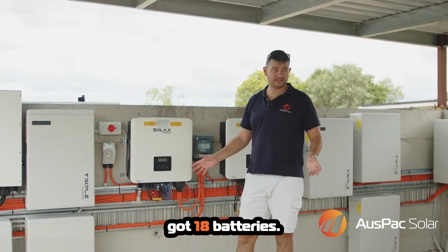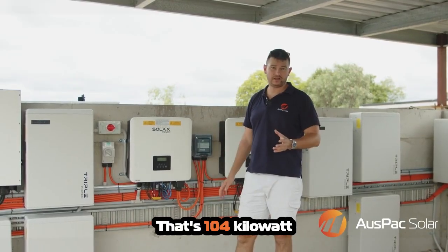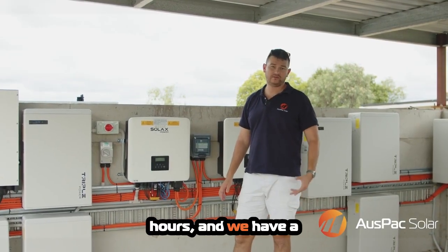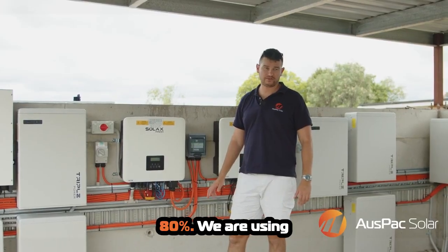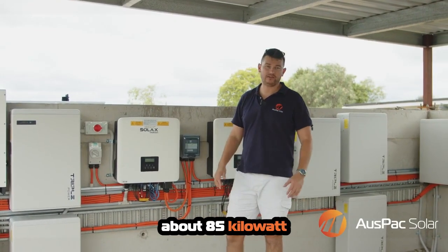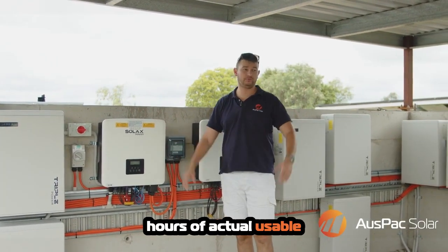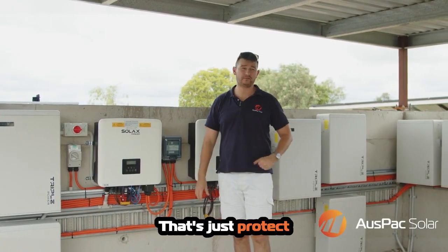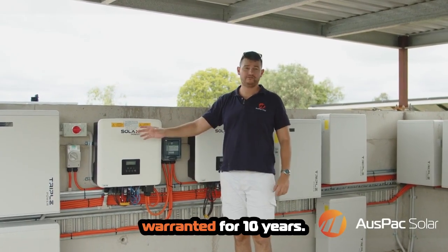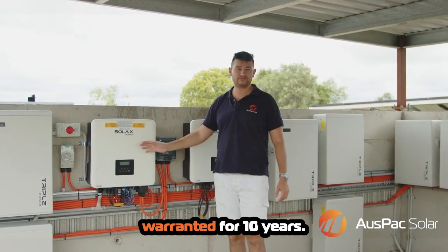On this site, we've got 18 batteries. That's 104 kilowatt hours. And we have a depth of discharge of 80%. We're using about 85 kilowatt hours of actual usable battery capacity. That's just to protect the batteries. The batteries are warranted for 10 years. The inverters are warranted for 10 years.